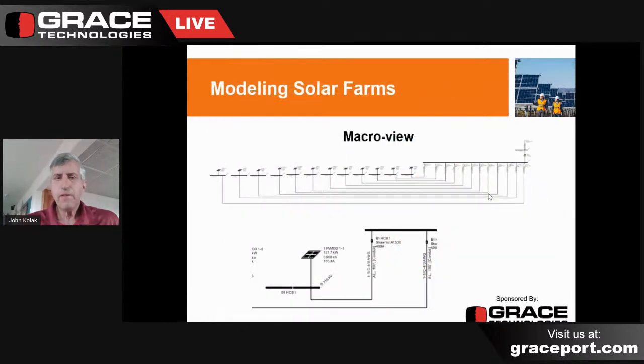Now, modeling solar and wind farms. I'm going to give you some insight here, and some of this, as I said, I've taken from other engineers that operated very clearly. From a macro view, the bus that you see to the right is actually the inverter. That's the incoming DC side of the inverter itself. What you see there are all the combiner boxes where we've aggregated all the arrays, and each combiner box represents the actual current that would be produced by the solar array in it.